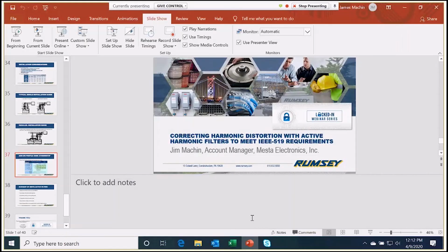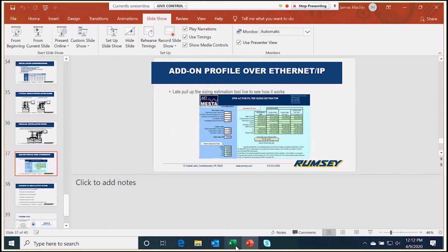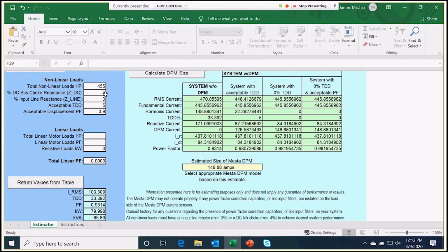Really easy when you're trying to size for an active harmonic filter. We just need to know the total horsepower that you're working with, if you're working with the drive with the DC choke, if you're working with line reactors, and what part of the band we're falling into: 5, 8, 12%. We normally would be happy to do this for you. We take a look at one lines and equipment lists all the time to say, what size filter do you need?